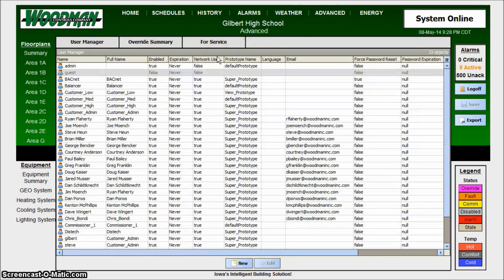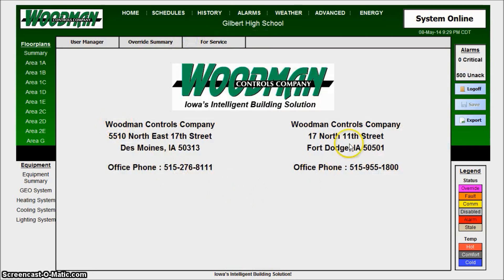The Advanced Summary is something newer we've started. It includes a User Manager, an Override Summary, and a For Service tab. The For Service tab lists our current phone numbers and addresses so you can always reach us. The Override Summary takes a little longer to load because it scans the entire building — all systems, all control points — looking for anything in override or alarm. This is a really great feature. When you have a big building and you've been making changes for days, weeks, months, or all summer, you can easily see what you've left overridden, like an economizer overridden shut.